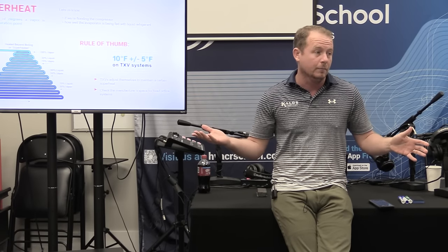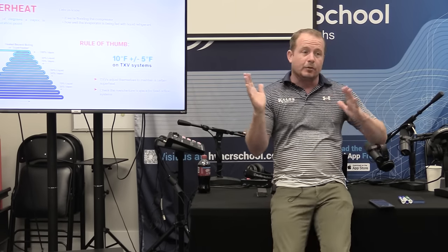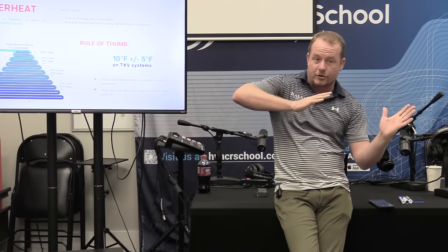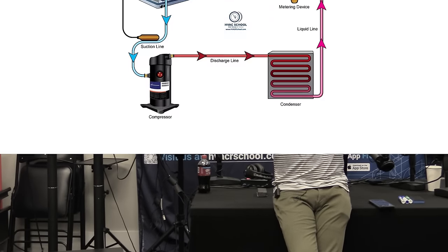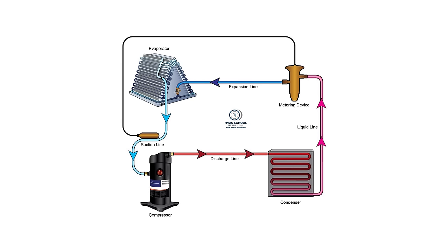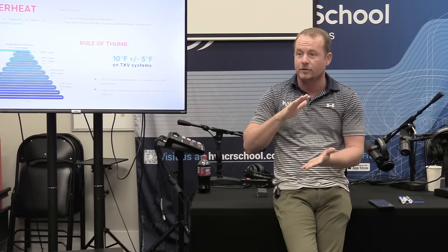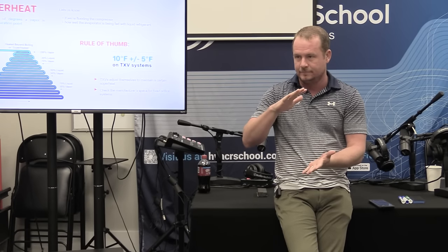We want a cold evaporator coil, but we don't want it too cold. Why not? It could freeze up. We also don't want it colder than it needs to be, because when we talk about compression ratio, that means lower pressure gas going back to the compressor. If it is lower pressure, that also means it is lower density — it's lighter.